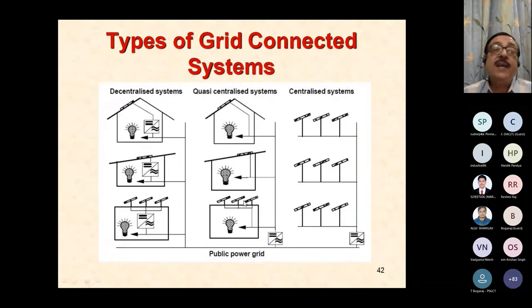Now, solar grid-connected systems can be of multiple types. Decentralized systems, where all the houses down the road have their own panel to AC conversion systems and they are being connected to the grid. Or in a society, every house decides to convert it to DC, common DC bus, feed the power into the DC, and there is a central inverter in the housing society which converts DC to AC.